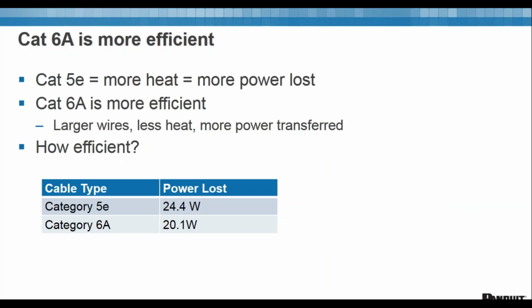And the reason why is that when you look at it, the end device will get 71 watts. Remember I said it doesn't matter how long of a channel you use, what type of cable you use, as long as it's a compliant 5E or 6A system. The source is going to send as much power as needed to ensure that that power device gets the 71 watts it needs. So when you're using a 6A system, that power sourcing equipment doesn't need to send as much power out because not as much will be lost through the cable. The PSE and the PD talk to each other. For a 5E system, you will need to send out a little bit more power to ensure that that power device gets what it needs.